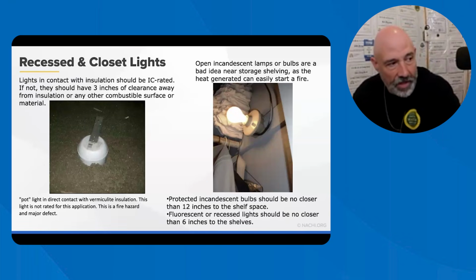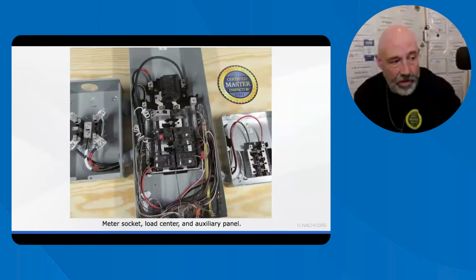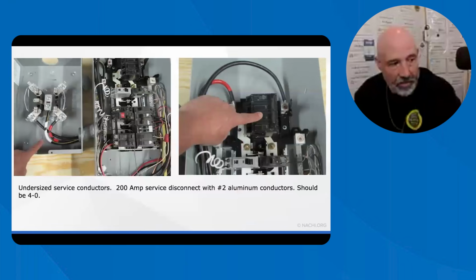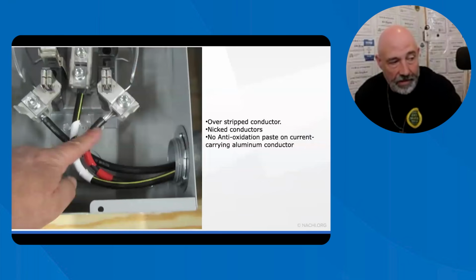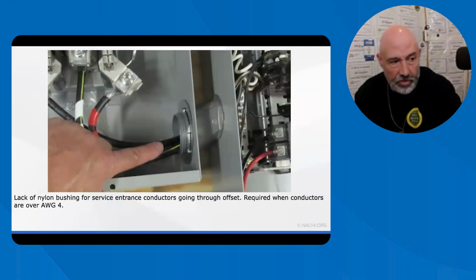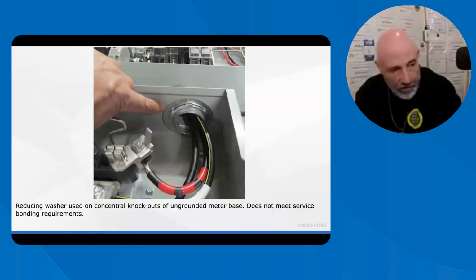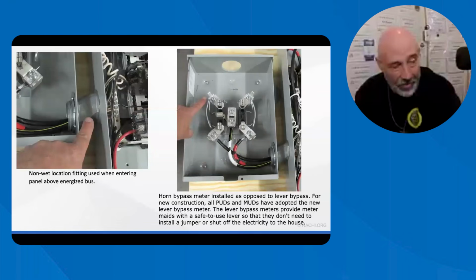Recessed lights, some of them with incandescent light bulbs, should not be used in a closet. That's what I just explained. Some of those light fixtures shouldn't even be touching anything electrical. Here are a couple of meter sockets and auxiliary panels that you see. Make sure you're testing those AFCIs and checking what wire size is going into those panel boards. If you see something like this, where there's too much wire sticking out, give your customers a good understanding. Make sure the bushings are where they're supposed to be so the wire doesn't get trapped. Here's another example of a knockout that doesn't really meet bonding requirements, so I would run a separate bonding wire to that.